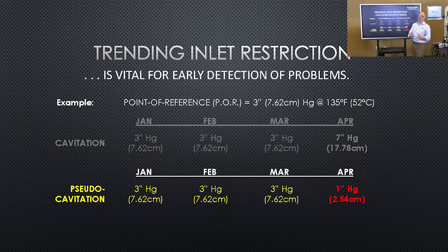If it's just production and I'm going to blow pump parts away, that's fine. If we have the money to mitigate that, no problem. However, before I worry about that, I have to worry about whether it will render the machine unsafe. That's why when we see abnormalities in the performance of hydraulic components, we need to address them immediately. No waiting. All right, so now we're going to look at what happens when the inlet restriction goes down.